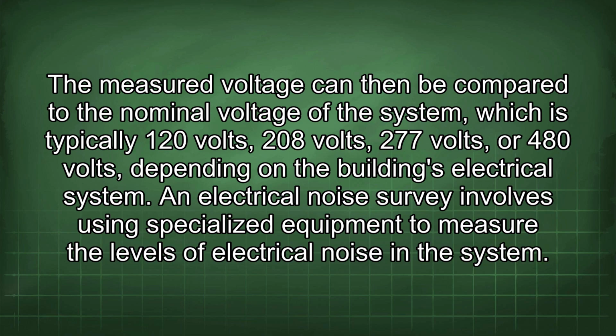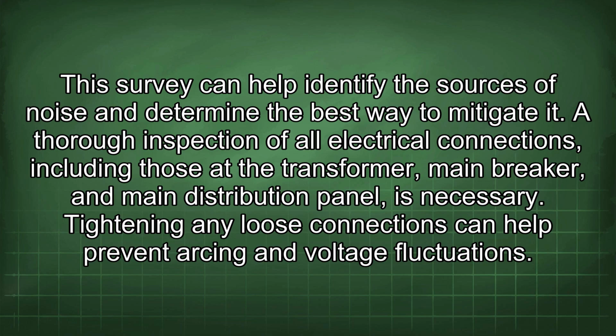An electrical noise survey involves using specialized equipment to measure the levels of electrical noise in the system. This survey can help identify the sources of noise and determine the best way to mitigate it. A thorough inspection of all electrical connections, including those at the transformer, main breaker, and main distribution panel, is necessary. Tightening any loose connections can help prevent arcing and voltage fluctuations.